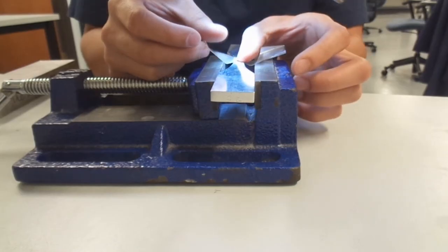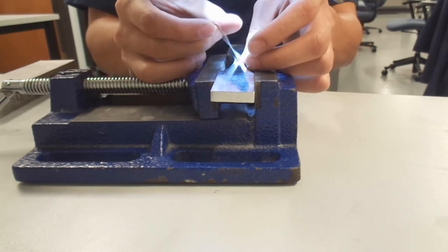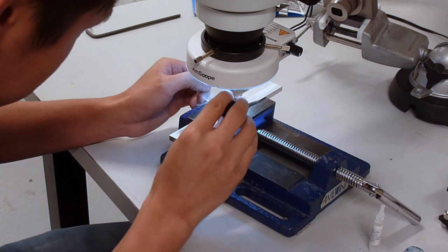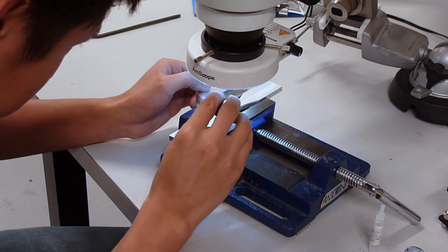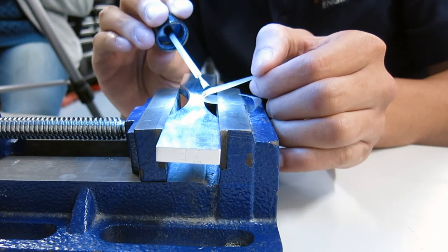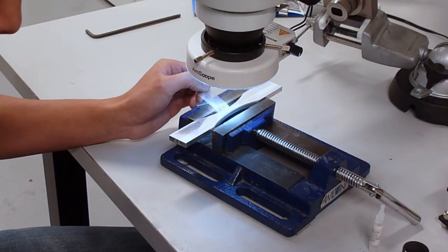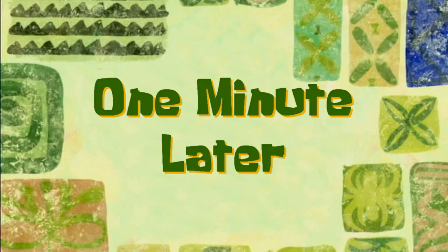With the gauge in place, lift one end of the tape and pull at a shallow angle. Roll back the installation tape and with your free hand, apply a thin, uniform coat of catalyst on the exposed surface of the strain gauge and the terminal pad. Allow this to dry for 60 seconds.